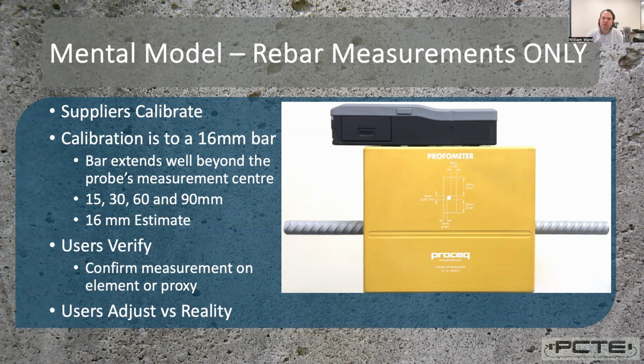And then there is the accuracy. So that is how close to the expected value we are. So we allow at 15 and 30 millimeters a plus or minus 1 millimeter difference at the moment of calibration. So that's how we achieve the presented accuracy under ideal circumstances. On the 16 millimeter bar, we have a 1 millimeter change, and we allow 2 millimeters at the 60 and 90 millimeter range.